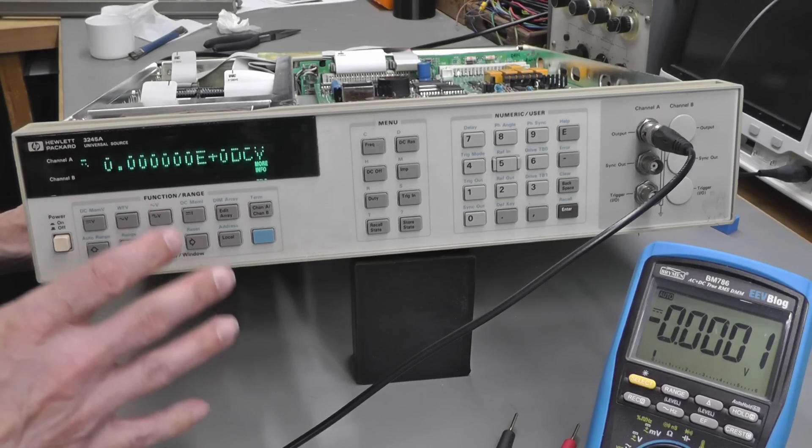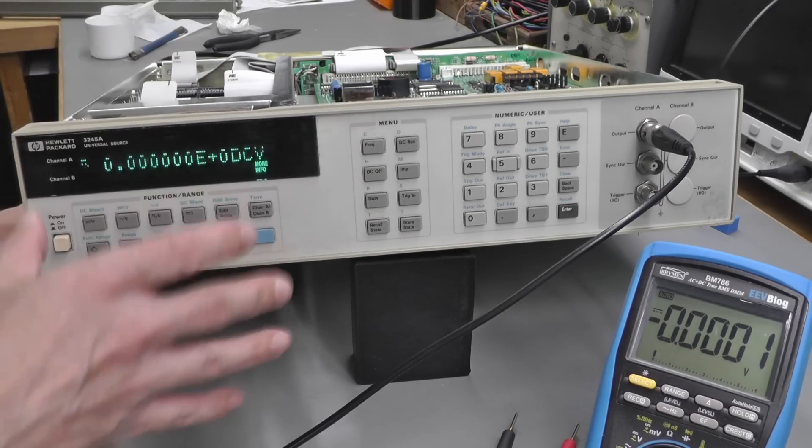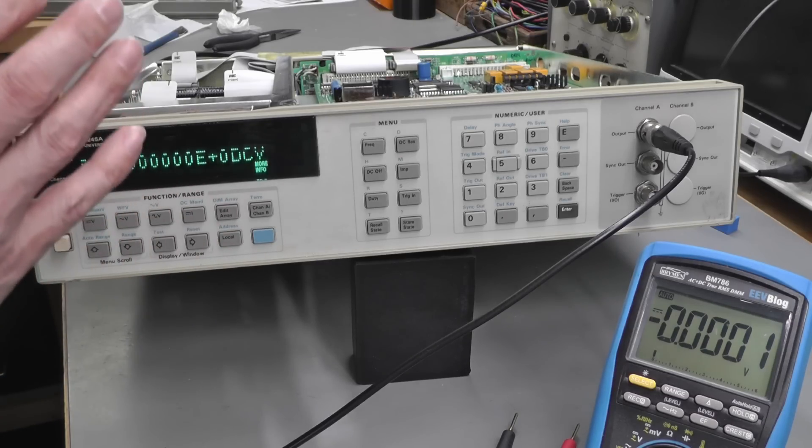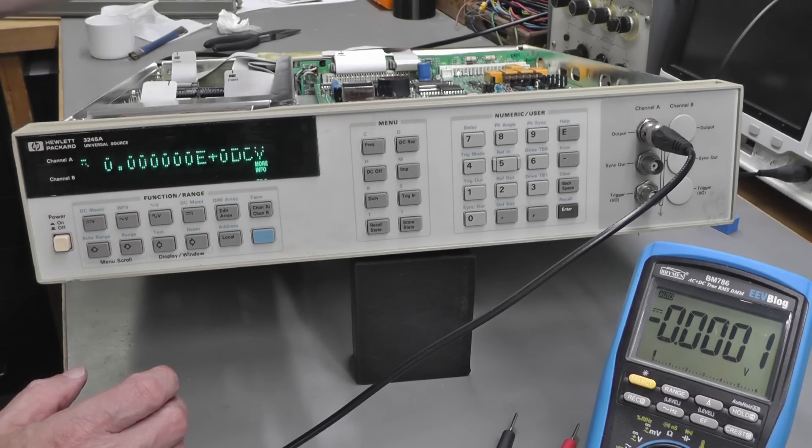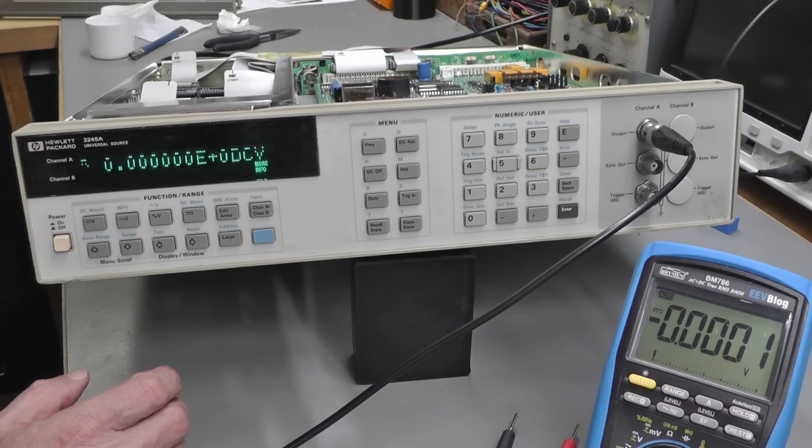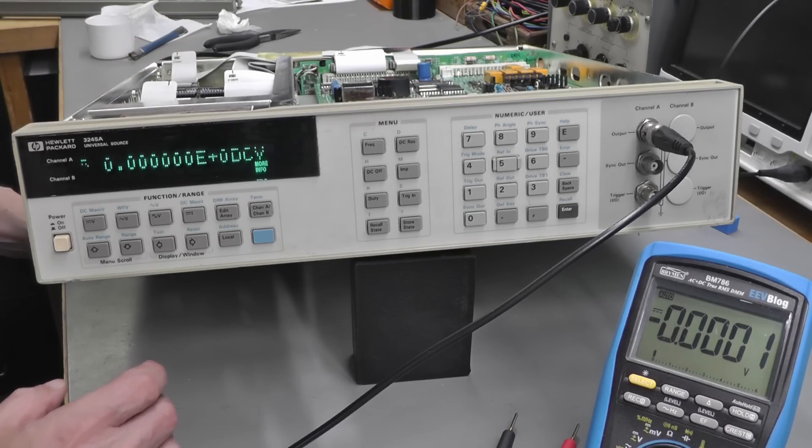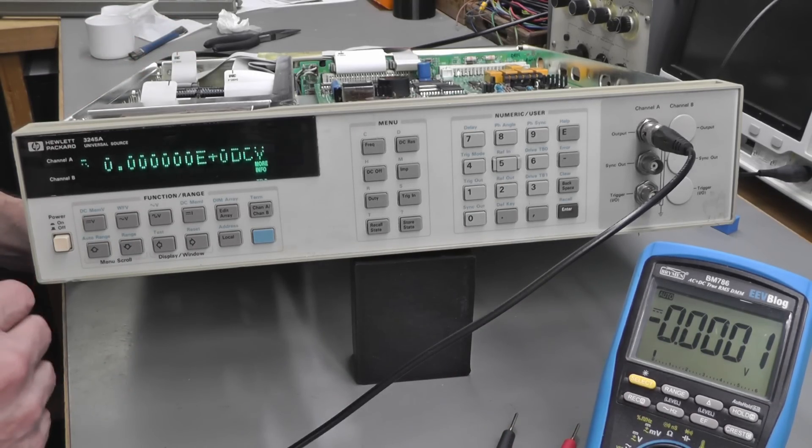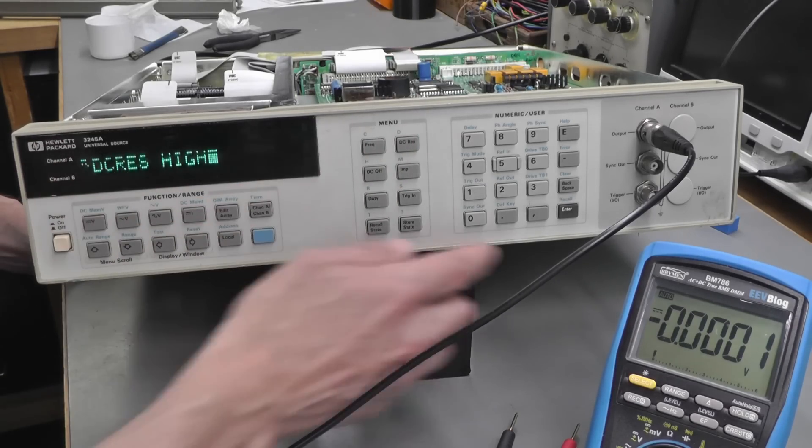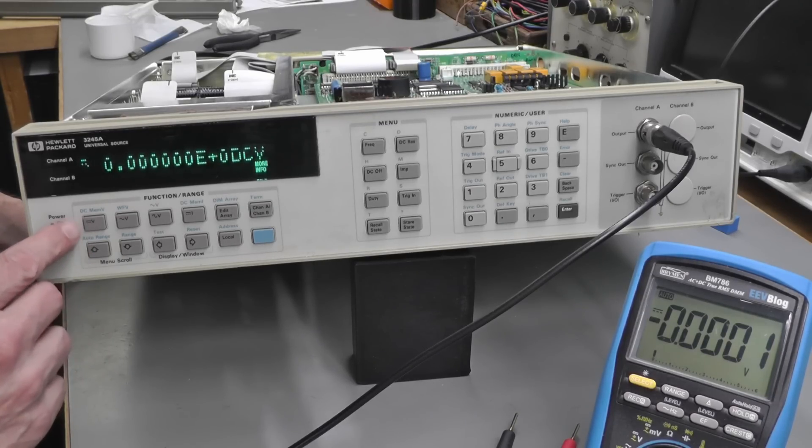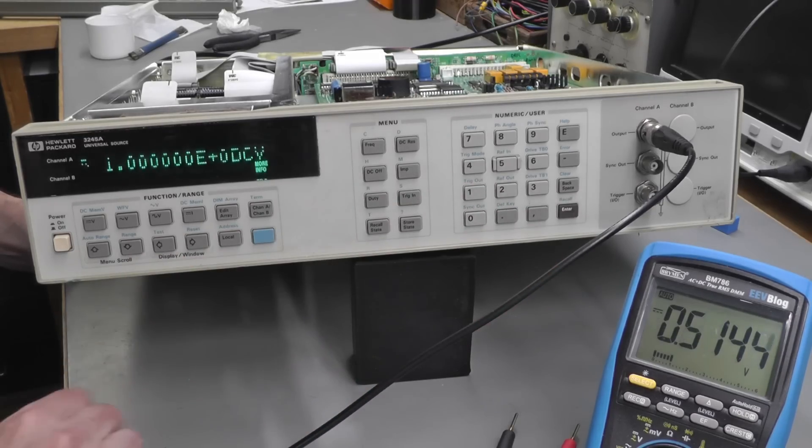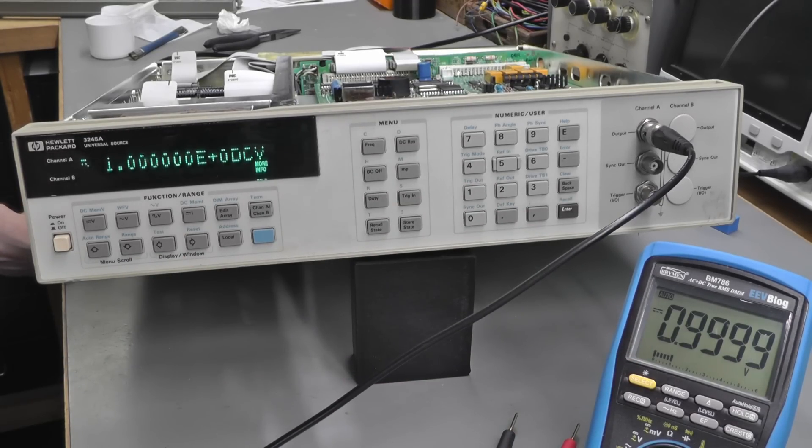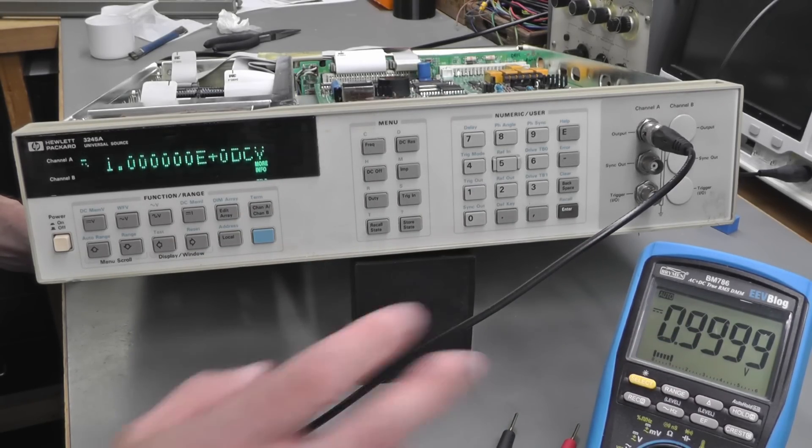But the crucial thing is, will it actually output? Now I believe it should still be calibrated because as I understand, the calibration data is actually stored on an EEPROM on the A1 board. The Dallas RAMs I've just replaced are purely for all the settings. So let's try an output. I've got my multimeter hooked up, so let's try—well, put it in high resolution mode first, should already be but just to be on the safe side—and we'll go for 1 volt.